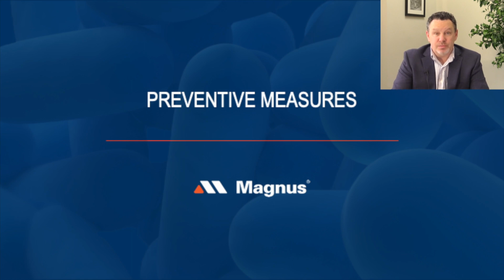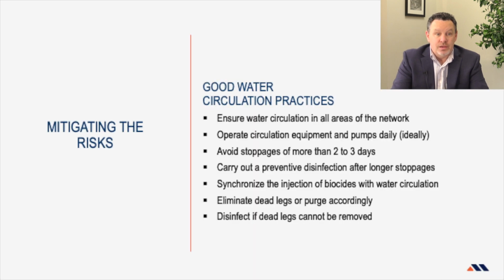So now that we know some of the risks, let's look at some preventative measures to help mitigate those risks. Like I said before, stagnant water is an enemy. So promote the circulation in the piping and the equipment. Avoid having heat exchangers that are offline. When a biocide is being injected, ensure that the whole system sees and is exposed to the biocide. Time the biocide injections with automated circulation pumps or valves opening up. Make sure that the proper treatment is reaching each of those layers in each of those piping systems.